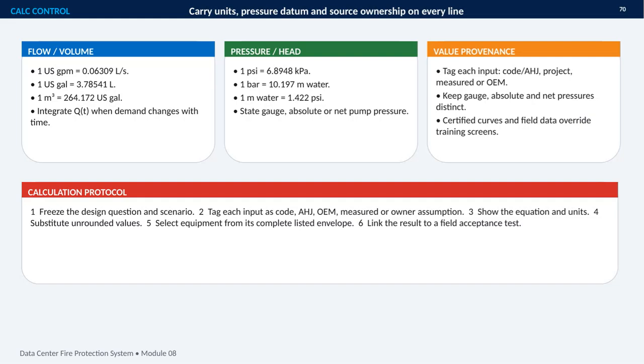This slide establishes the control discipline for calculations in the fire protection system. The central rule is simple: carry the units, pressure datum, and source ownership on every line. That means distinguishing flow from volume and documenting whether pressure is gauge, absolute, or net pump pressure. For flow and volume, 1 US gallon per minute equals 0.06309 liters per second. 1 US gallon equals 3.78541 liters, and 1 cubic meter equals 264.172 US gallons. When demand changes over time, the total volume must come from integrating the flow rate, Q of T.